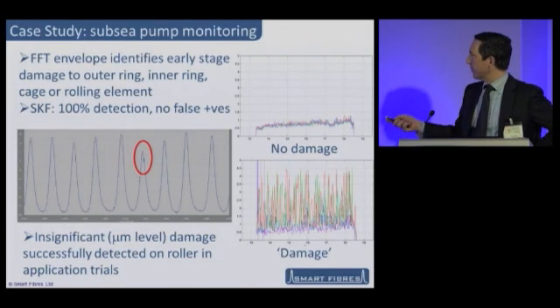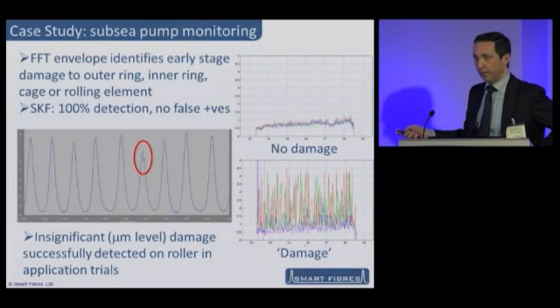And these are tiny strain signals. That's 5 microstrain. And the scale is the same on both plots. But you can see there's a big difference between this one here and this one here. And we determined the difference comes down to this rolling element here. Every time this one rolling element passed its respective sensors, we had a peculiar little glitch.